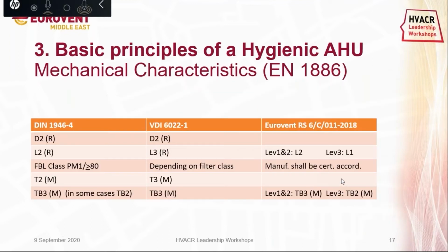Mechanical characteristics of the casing is another requirement in hygiene norms. For different classes of hygiene levels, casing of a hygienic AHU shall comply with some minimum classes with respect to EN 1886, regarding the casing strength, casing air leakage, filter bypass leakage, thermal transmittance, and thermal bridging.